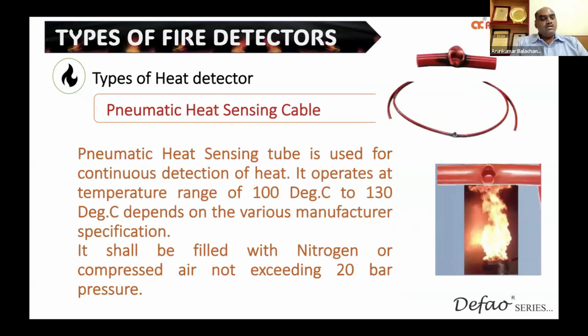The new type of heat detector is the pneumatic heat sensing tubes. These tubes are special polymer tubes filled with 15 to 20 bar of nitrogen, and they will operate, or burst, at a temperature between 100 to 130 degrees centigrade. This type of tubing is often coupled with a small extinguishing system, and it is widely used in protecting small UPS or server cabinets for a localized kind of protection.